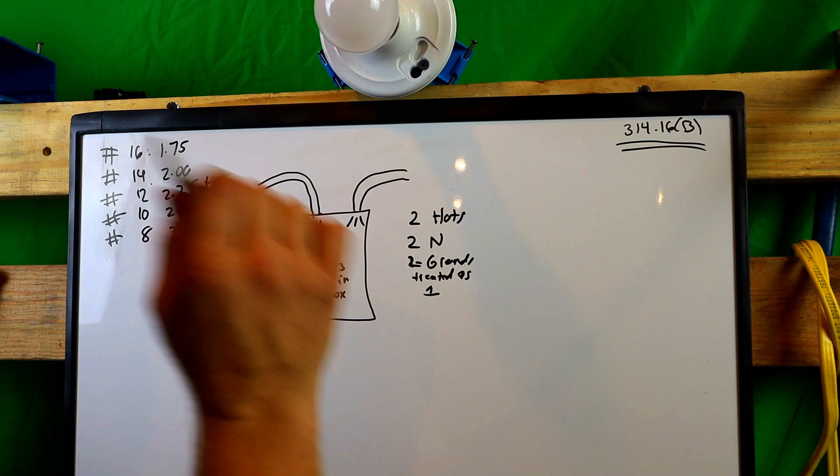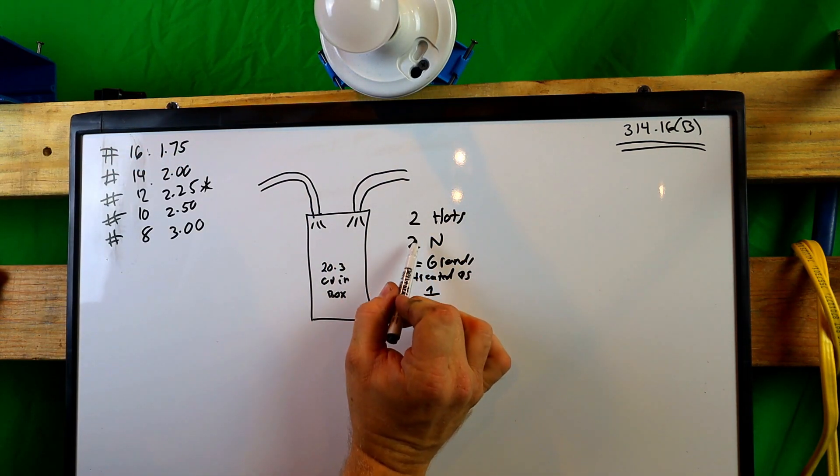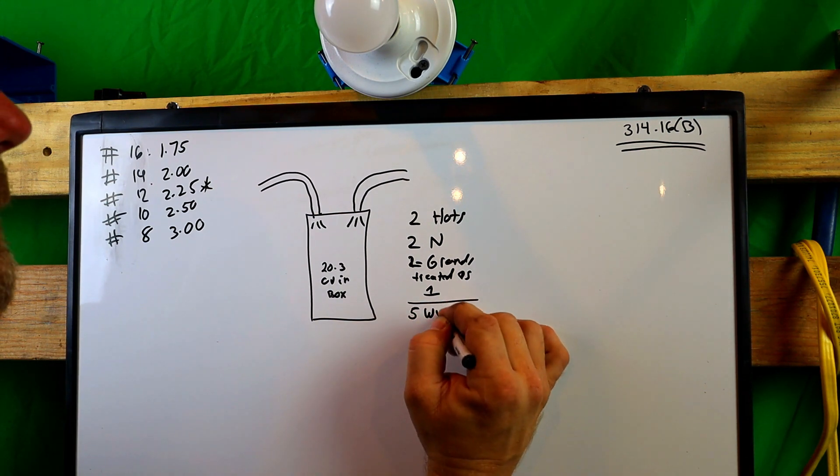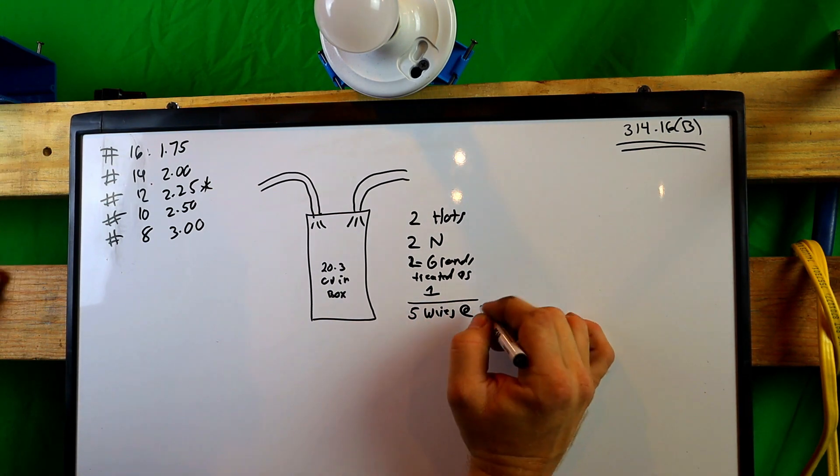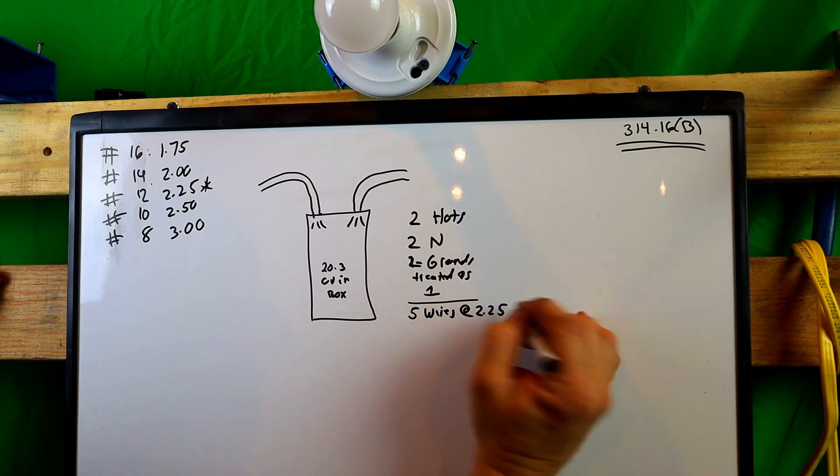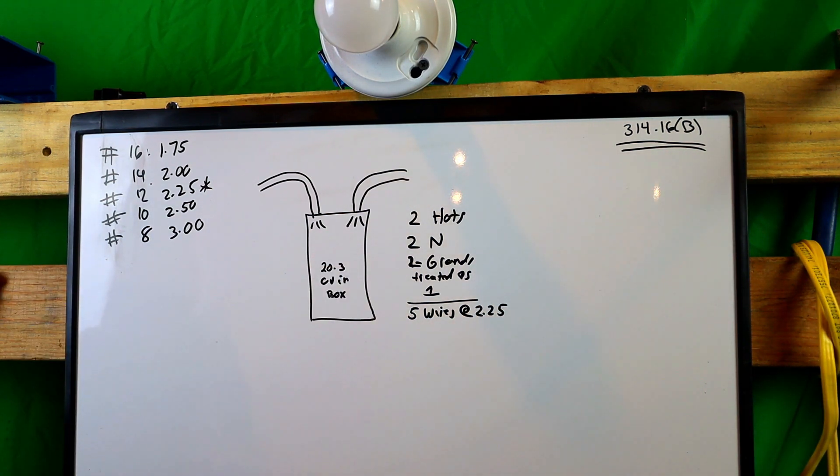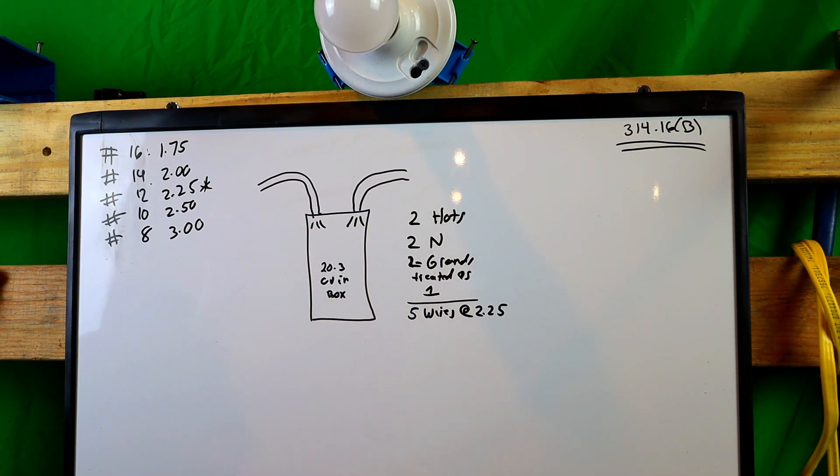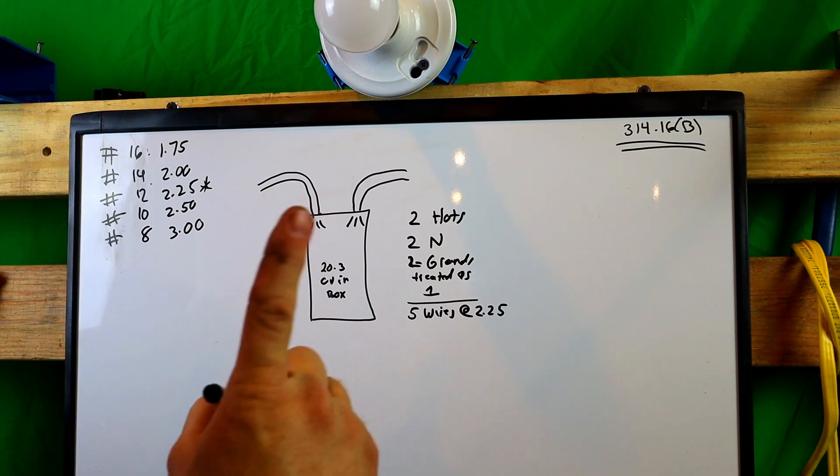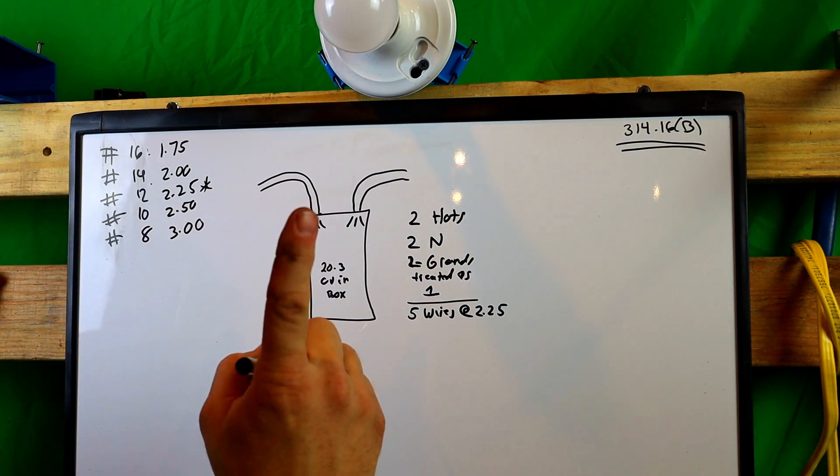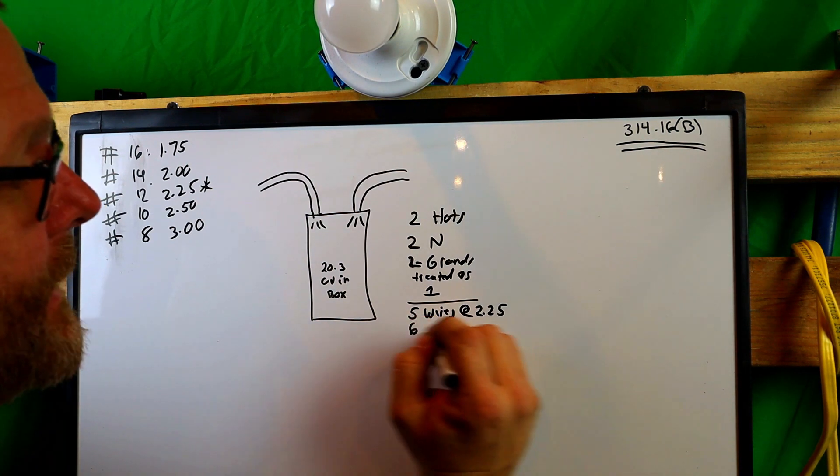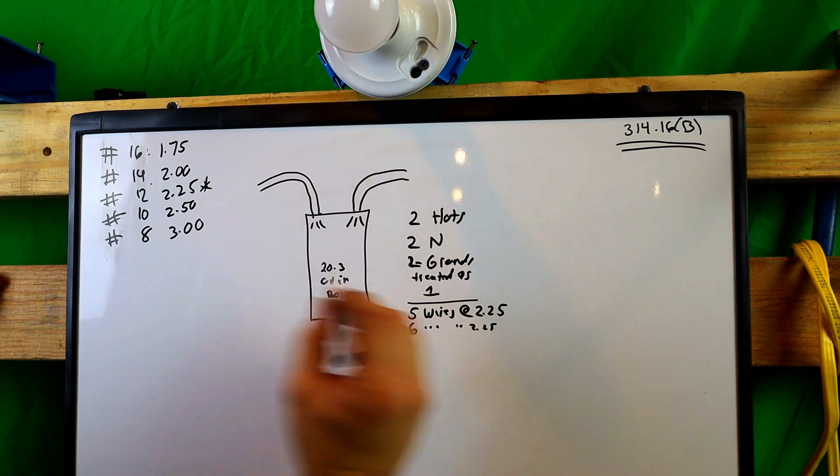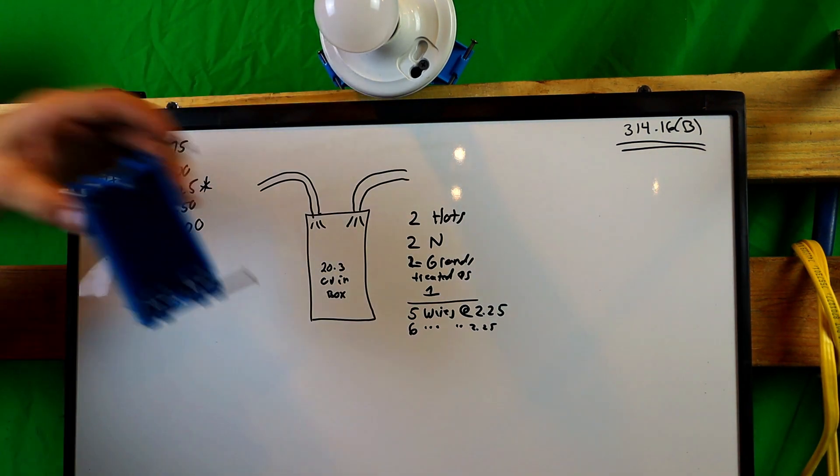Does that make sense? This is in the code book. You can read this straight out of the code book. So we technically have five wires. So we have five wires at 2.25. Now, what else do we have to count in this box? Well, we know that there's internal clamps in here. So we have to count that as one wire size. So there's now six wires at 2.25. And we're going to put one receptacle in here because that's what we're going to use. So let's talk about receptacles.